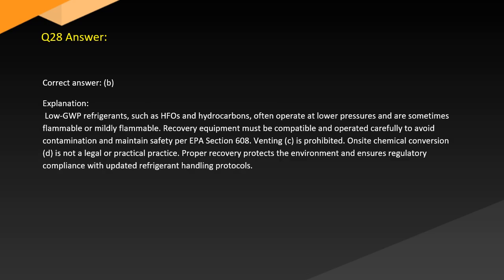Answer. Correct answer: B. Explanation. Refrigerants such as HFOs and hydrocarbons often operate at low pressures and are sometimes flammable or mildly flammable. Recovery equipment must be compatible and operated carefully to avoid contamination and maintain safety per EPA Section 608. Venting, C, is prohibited. On-site chemical conversion, D, is not a legal or practical practice. Proper recovery protects the environment and ensures regulatory compliance with updated refrigerant handling protocols.